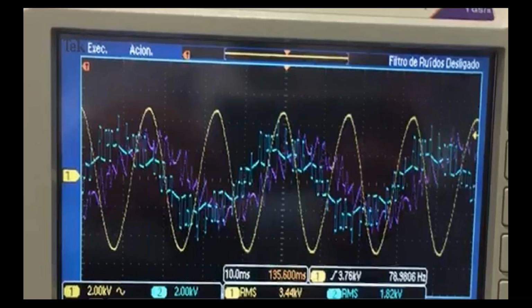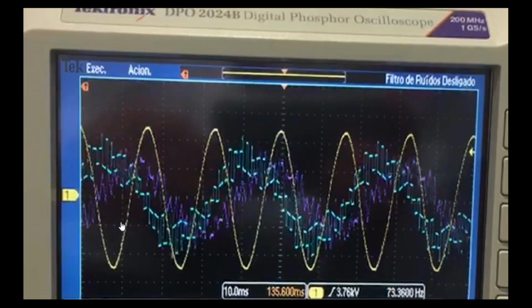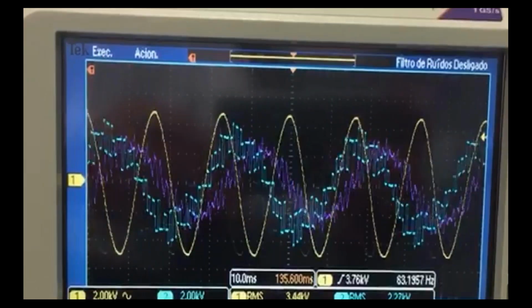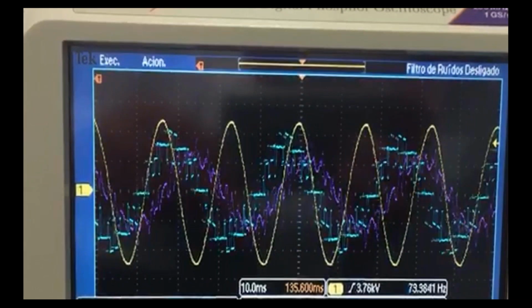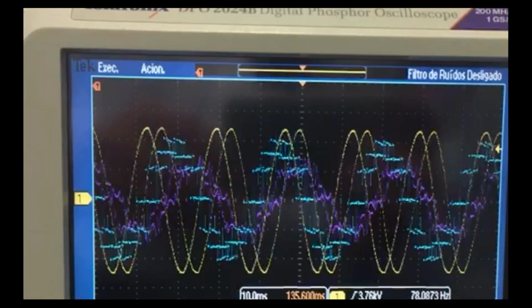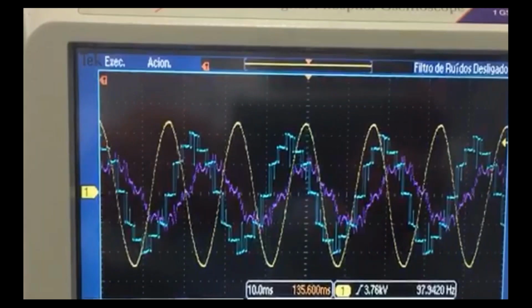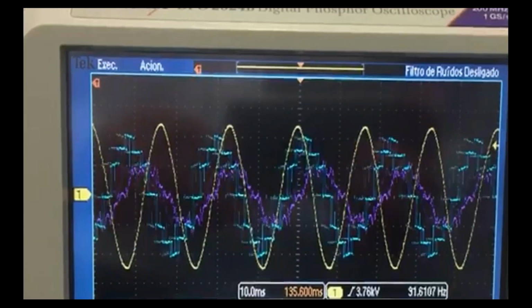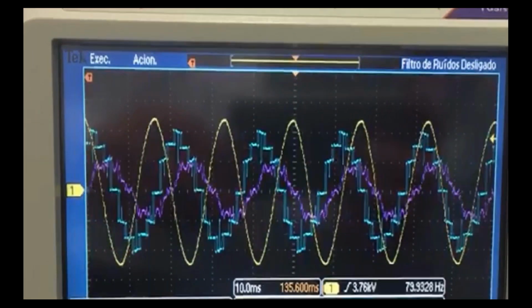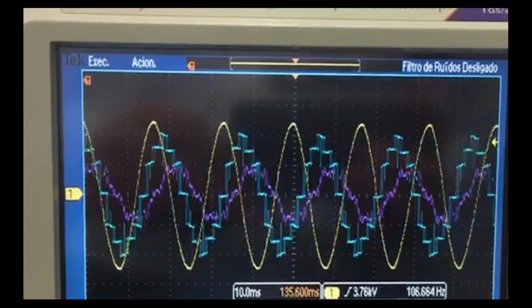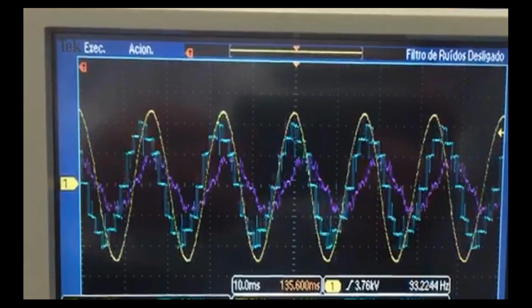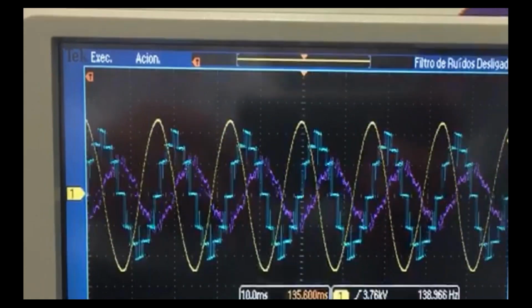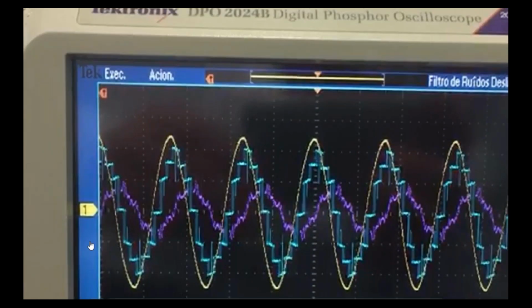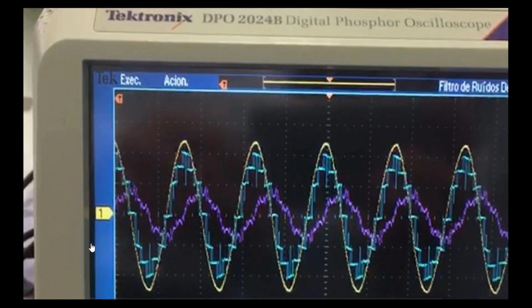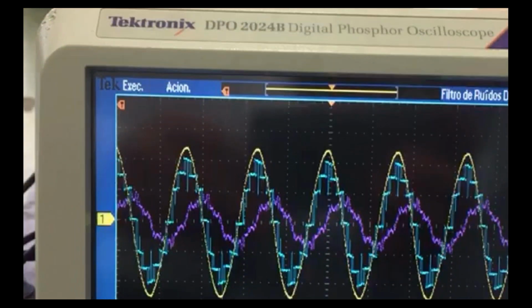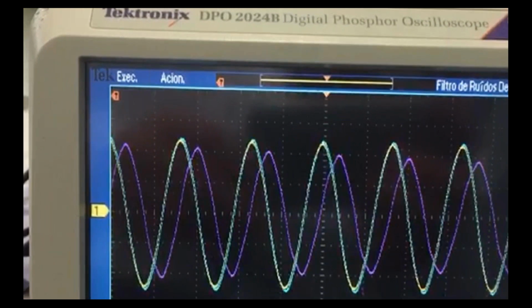So you'll see we are supplying the voltage to the motor from the VSD only. The synchronism relay is trying to find synchronism between the supply voltage and the VSD voltage. It's hunting, trying to search for synchronism. Now we've found synchronism, so now we can close the bypass contactor.